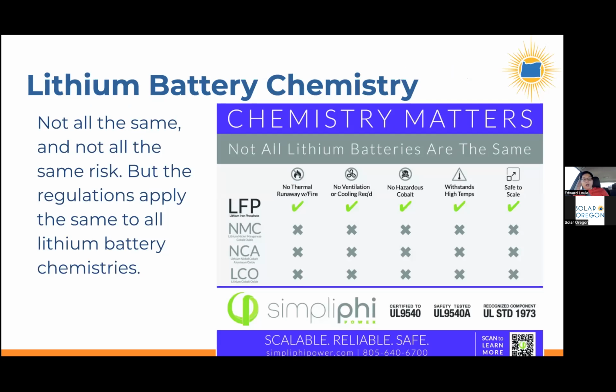And as you'll see in some of the videos showing the comparison, ranging from dramatic explosion to very anticlimactic problems when you overheat batteries and or short circuit them. Doesn't matter. Currently, the code is that if it's a lithium battery, you have to do the NFPA 855 rules and the UL testing. Even though there are chemistries like lithium iron phosphate, there are really not that many good examples of lithium iron phosphate batteries failing in a dramatic fashion, because you can drill a hole right through one cell and it will not blow up fantastically. So it's a very safe chemistry. But right now, the NFPA and UL doesn't care about that. You can have lithium iron phosphate battery home energy storage systems, and you still have to comply with those rules. I'm not thrilled about that, but that is what it is right now.